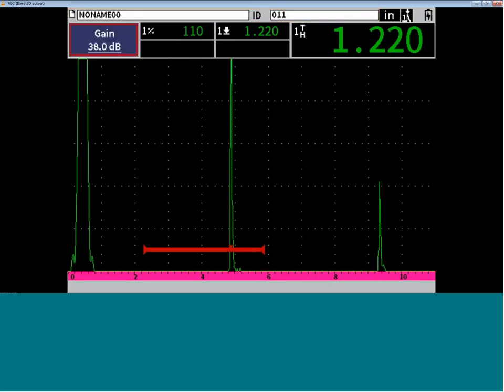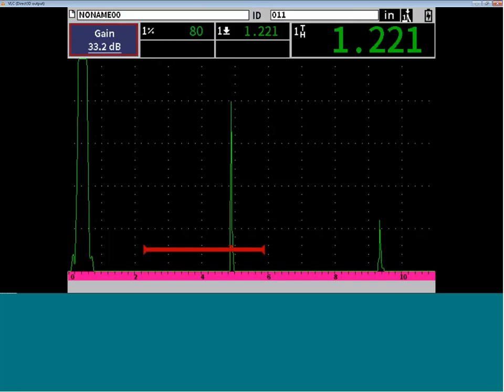Another area that's particularly useful is when highlighted on the gain function, pressing the Enter key allows direct access to the famous Auto 80 function for the EPOCH series, which dates back to our EPOCH 4 instrument from the early part of the 2000s. This Auto 80 function is very easy to access from gain, from our home area of the screen, and provides dynamic gain access, very rapid gain adjustment to a fixed target of screen height. Of course, Auto 80 is the default, but as a user, you can prescribe that to be Auto 100% or Auto 60% or any other target reference height that's required by your particular inspection. So there's quite a bit that can be actually performed from this main inspection screen on the EPOCH 6LT.